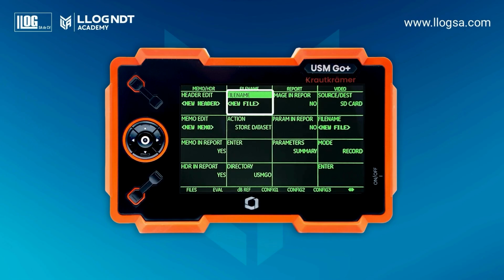If we want to save a calibration, parameters, or a report, we assign a file name and move to the Enter option, confirming with the center button. We can also choose the storage folder. When saving a report, we can add an image of the A-scan and the list of parameters. To include them, simply activate the Yes option for each function. It is also possible to view and save the complete list of current parameters.